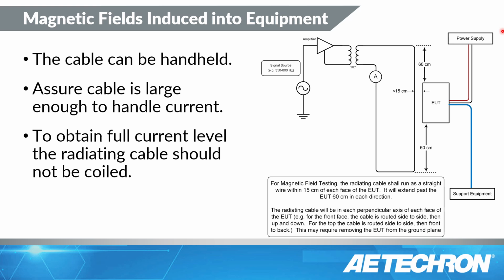But you're going to do 5 faces. You do not have to do the bottom. The 5 faces will have 2 axes, so there's essentially 10 tests that you're doing. And if you have to do 2 different frequencies, 350 and 650, that's 20 tests. For these tests, you're dwelling for 10 seconds on each face, so make sure that you are leaving an adequate amount of time for exposure in each position.